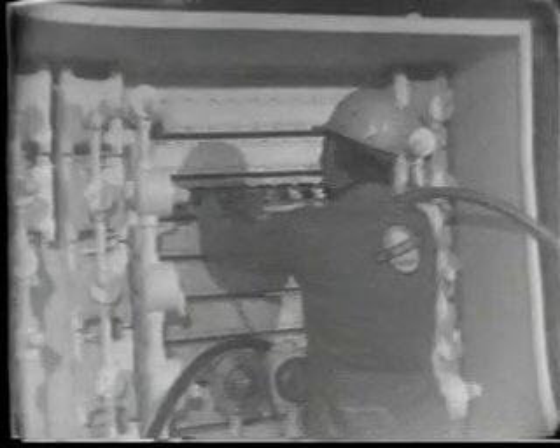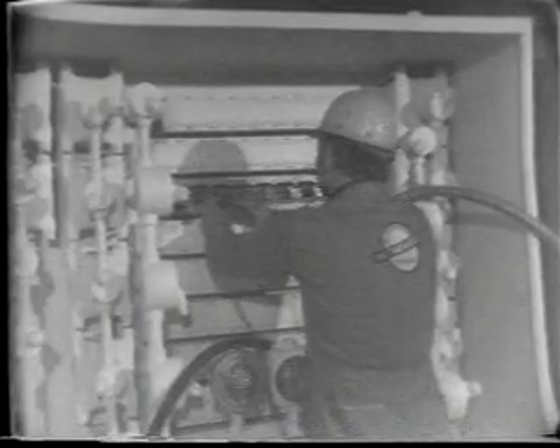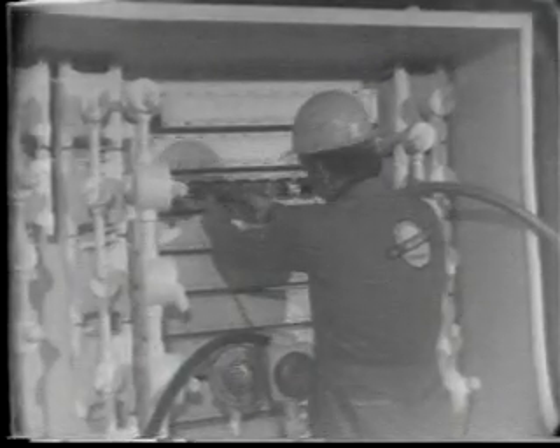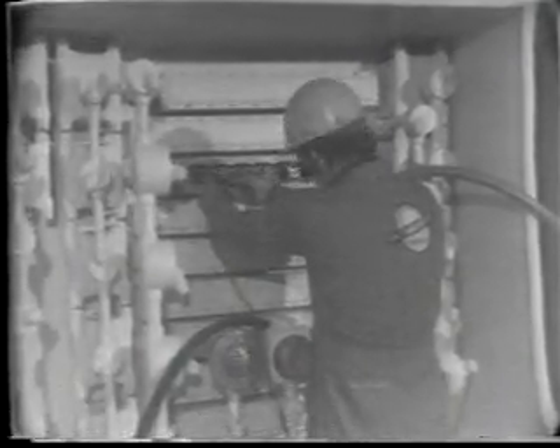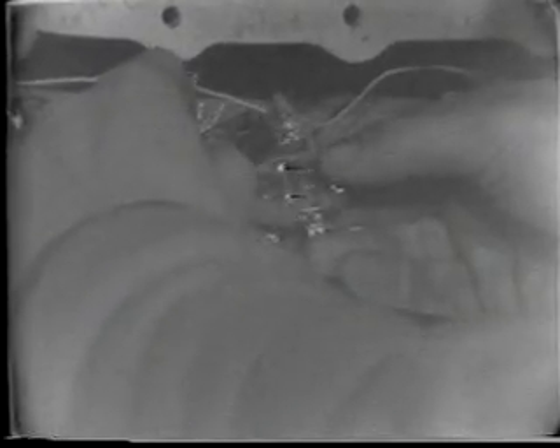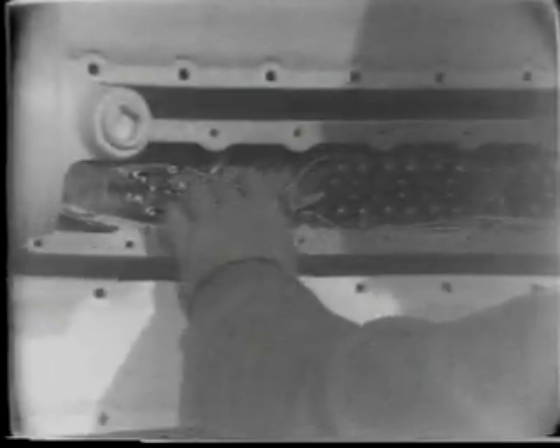If the solenoid can be energized from one panel, but not another, this tells you that the problem must be in the first panel or the interconnecting cable. Be sure to check the switch contact block on the non-operating panel. This is done by turning the power off, removing the wire, and checking continuity between the contacts. This should be an open circuit with the switch not depressed, a closed circuit when the switch is depressed.